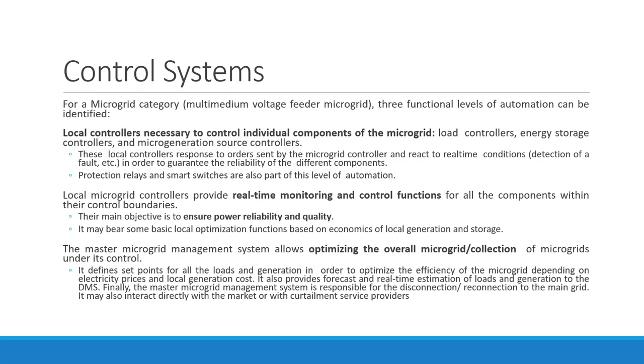Means possibly, suppose you are having the diesel generation unit, and you are having the renewable generation. Your renewable generation is sufficient to meet the local demand. At the same time, the energy which is available from the diesel generation is surplus, and you are selling it. But the price at which it is sold is not beneficial. So this optimization function will say, instead of generating electricity from the diesel generator, stop it. Do not generate from the diesel generator because it is not economically beneficial. So that generation will be stopped using the optimization function, and the local demand will be met by your renewable generation. So this could be a possible case.